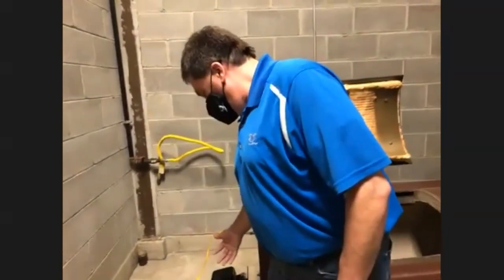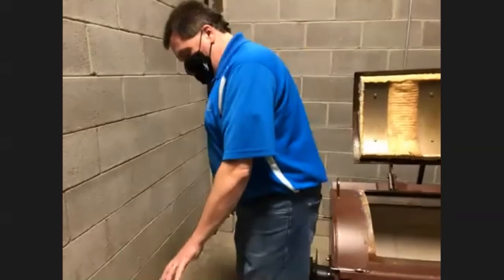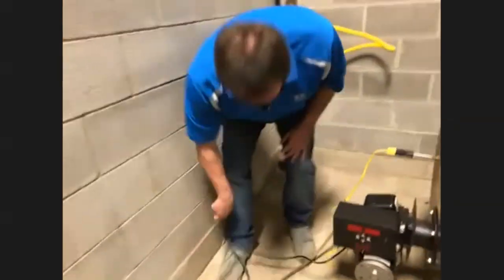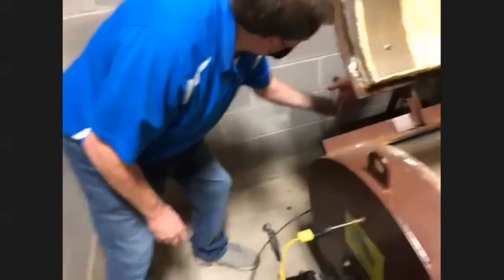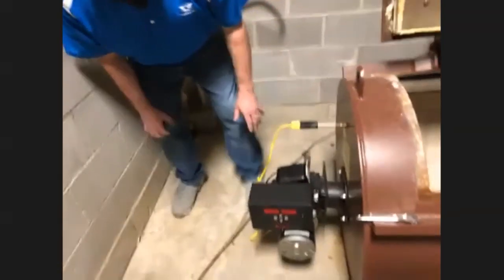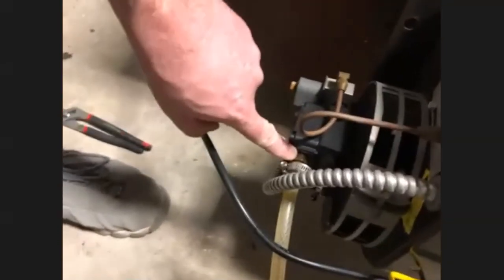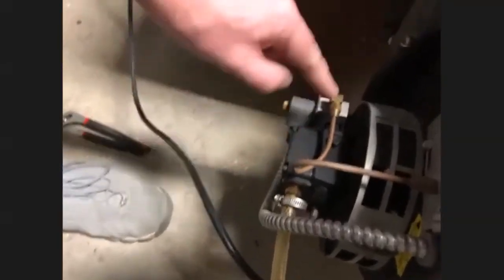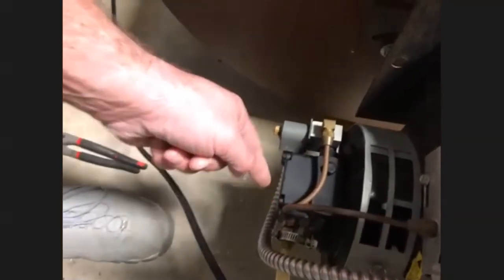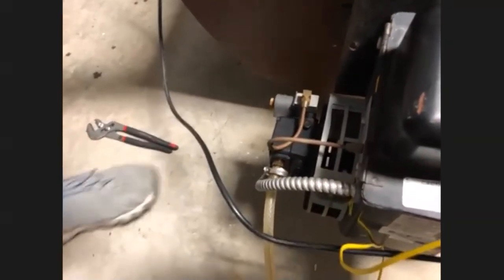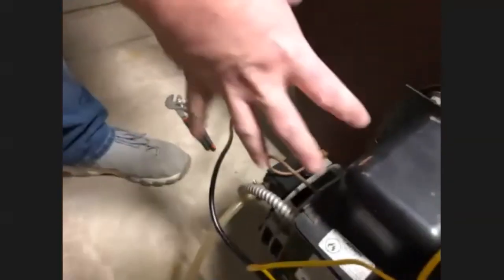When you're operating oil burners, what we have set up here is a bypass setup with the fuel supply. What that means is we have one plumbing system hooked up, and there is your input right here. Since this is a bypass system, any excess fuel is going to bypass and continue to recirculate in the pump and get reused inside here. If you're doing a non-bypass system, which I recommend because it's a little bit more efficient, it allows the pressure to come through a lot easier.